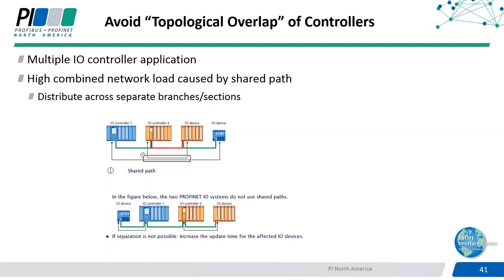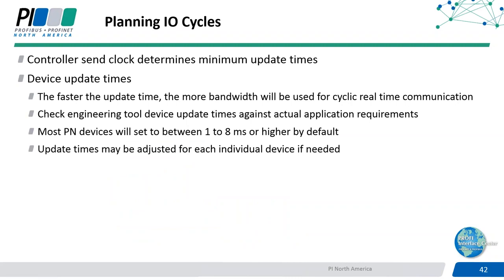If that's not possible, then you probably need to look at the update time and set that to a slower rate on the I/O device. And so, speaking of update rates and planning I/O cycles, when it comes to planning these I/O cycles for the devices, each PROFINET controller has a minimum send clock value, and that's typically going to be 1 millisecond. You can adjust it on some controllers, but most of the time you're going to stick your controller in there, and it's probably going to be 1 millisecond on your PLC.